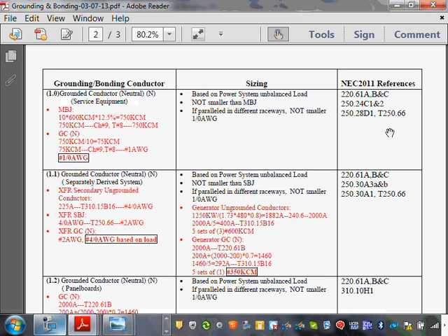In no case shall your neutral be smaller than what? The system bonding jumper. In no case can your neutral be smaller than the system bonding jumper, exactly like at the service. In no case shall your neutral or grounded conductor be smaller than the main bonding jumper. So that's the size of my neutral: 5 sets of 350 kcmil.